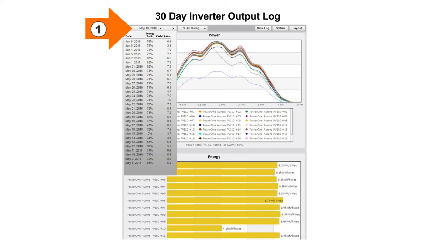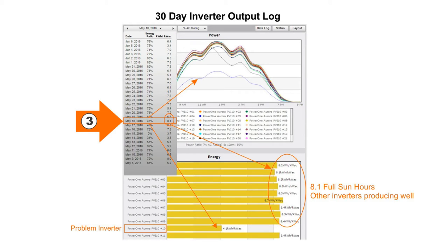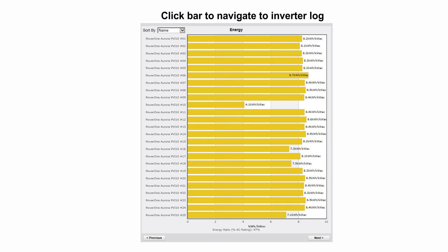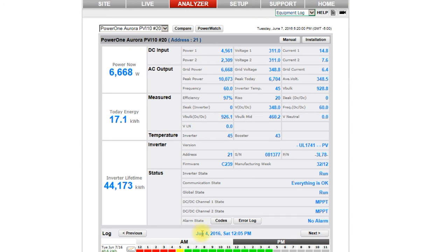To check inverter performance, use the 30-day log to see if its output is consistently below expected. Click on any date using the date pulldown box to see the power and energy chart for that day. View consecutive days with the next and previous arrow buttons. Look for days with a low energy ratio when the system output was operating near full capacity due to higher solar insolation. If the low output pattern from one inverter persists, further investigation is needed. Once you have determined which inverter seems to have a problem, use other analyzer tools to diagnose what to fix. For a shortcut to the 30-day inverter data logs, click on the energy bar for the inverter of interest — it will launch the inverter log where you can review all conditions registered by the inverter.